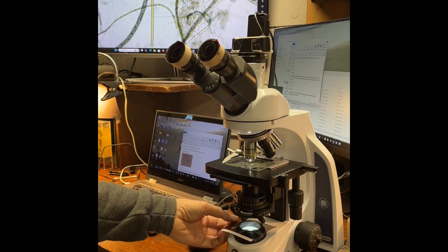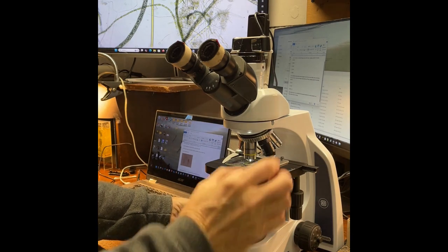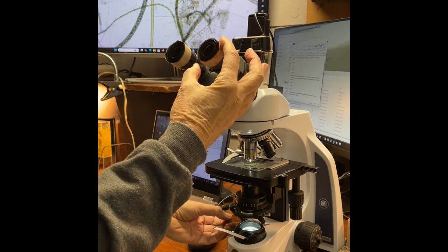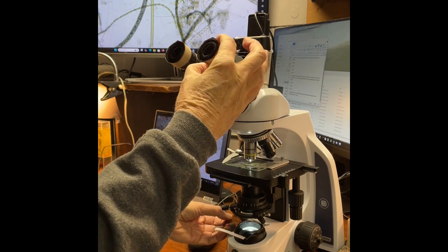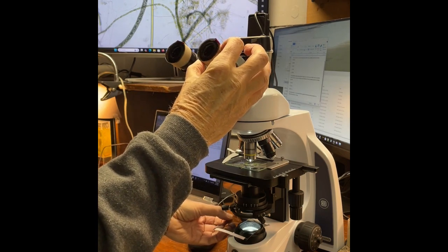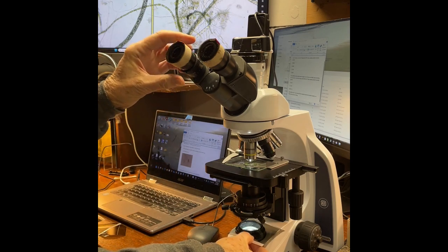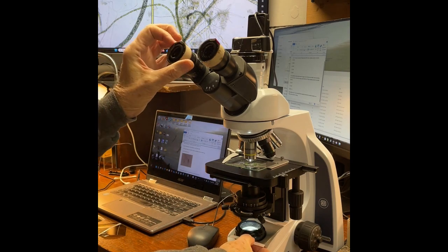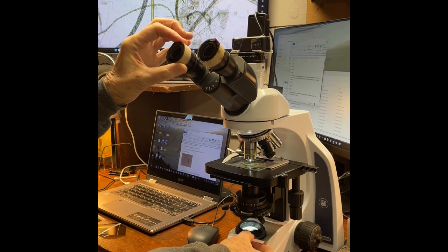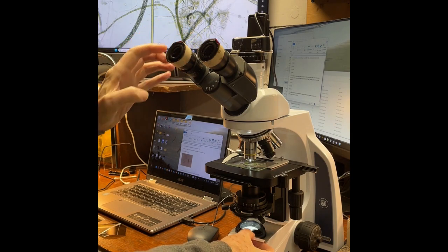To align the eyepiece filters, move the assembly so the right horizontal orientation side covers all the illuminator and rotate the right eyepiece filter to get the darkest view. Then move the assembly so the left side covers all the illuminator and do the same for the left eyepiece filter. Now you should be able to see the sample in 3D.